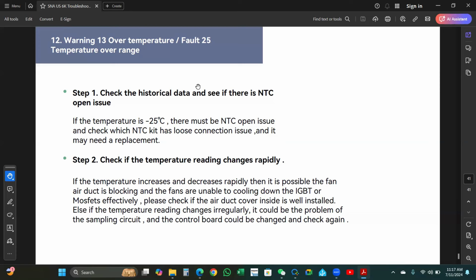Step 2, check if the temperature reading changes rapidly. If the temperature increases and decreases rapidly, then it is possible the fan air duct is blocked and the fans are unable to cool down the IGBT or the MOSFET effectively. Please check if the air duct cover inside is well installed. Otherwise, if the temperature reading changes irregularly, it could be a problem of the sampling circuit, and the control board could be changed and checked again.